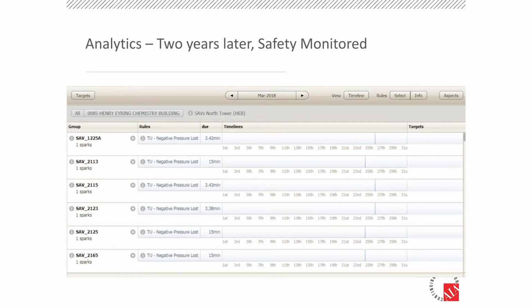So this is a 2-year fast forward to, again, negative pressure loss. It was something we rigorously looked at every month. There's a couple little blips on here. This is 3 minutes, but you can see that the building had stabilized and they were consistently maintaining the lab pressurization that was required.